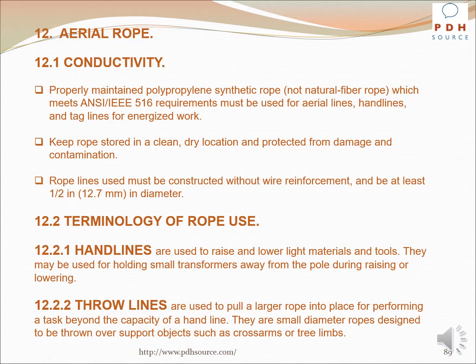With regard to aerial rope, properly maintained polypropylene synthetic rope, not natural fiber rope, which meets ANSI IEEE 516 requirements, must be used for aerial lines, hand lines, and tag lines for energized work. Keep rope stored in a clean, dry location and protected from damage and contamination. Rope lines used must be constructed without wire reinforcement and must be at least 1/2 inch in diameter. Hand lines are used to raise and lower light materials and tools. They may be used for holding small transformers away from the pole during raising or lowering.